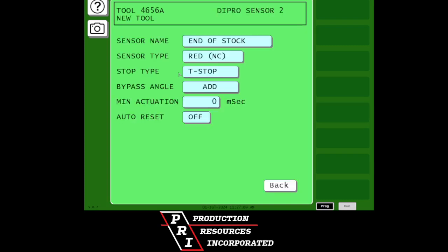In most instances, the programming of the red sensor is now complete. SmartPAC does offer additional features that may be used for certain red sensor applications. By definition, red sensors are static events that are monitored for the entire press cycle and will generate a fault anytime the sensor changes state. There may be instances where conditions outside of our control cause the red sensor to change state and may create what are known as nuisance faults.